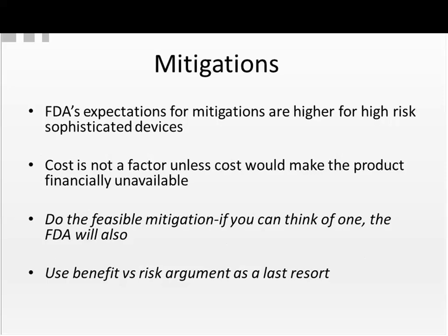Use a benefit versus risk argument as a last resort. FDA frowns on trying to use benefit versus risk arguments to get out of actually doing mitigations.